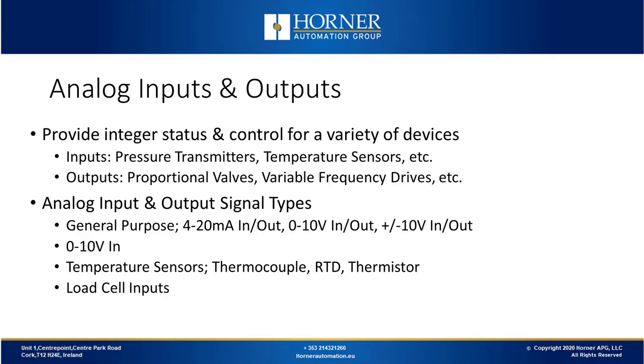On the analog side, we're talking about integer control or integer status, depending on whether it's an input or an output. For example, for inputs there's pressure transmitters, temperature sensors, etc. For outputs, you could be supplying a speed signal to a variable frequency drive. There are many different signal types for analog inputs and outputs. The general purpose ones are typically 4 to 20 milliamps or 0 to 10 volts. Sometimes you'll see plus or minus 10 volts, but not very often. There are many supported temperature sensors, including thermocouples, RTDs, and thermistors.